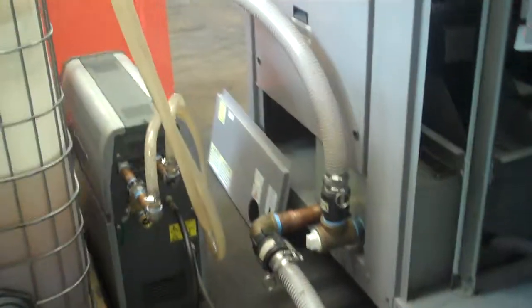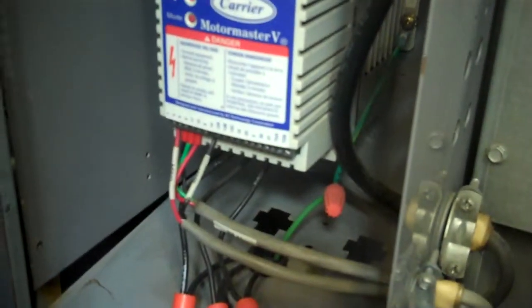Now this chiller is going to come with the Carrier storage tank option, which goes underneath the unit. We're going to show that in a second, but we have it integrated with our own tank now because this is a heated tank test system. The other tank that it's going to come with is simply the storage tank that goes underneath the unit. And ultimately we're going to make connections here to that storage tank. The unit has a low ambient option, which is this MotorMaster VFD drive, which is driven off of pressure of the system. This allows this to be an outdoor installation in colder climates year-round.